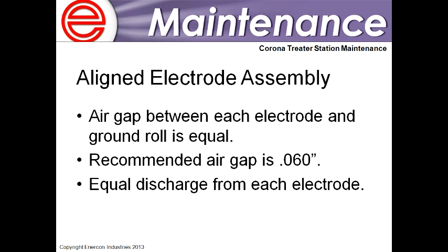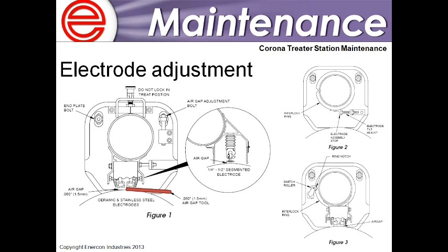And it's a balancing act. I'm not looking for precision necessarily, there's no tolerance per se. It doesn't matter if it's 52 thousandths or 60 thousandths. But really what we're looking for, whatever the electrode gap is set to, and our recommendation is 60 thousandths, is to make it as consistent as possible on all of the electrodes. Yep, and we do provide gap gauges that are 60 thousandths of an inch in thickness. If you don't have any gap gauges, or maybe you had some Enercon gap gauges and misplaced them, feel free to contact us and we'll be happy to send you some out.